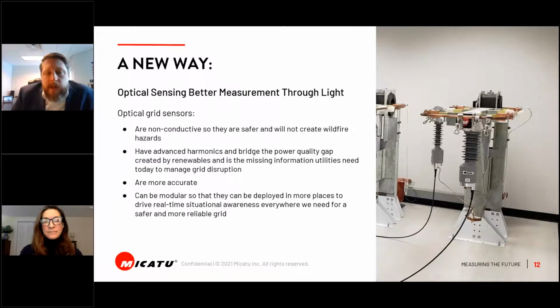The second thing is, because we're a field effect measurement technology, we have a large bandwidth. You're probably asking why bandwidth matters, it's because we can measure harmonics. Traditional technologies act like a low pass filter, whereas with ours we can measure up to the 250th harmonic in voltage and up to the 11th in current, and we're expanding the technology to measure even further. Harmonics for both current and voltage are of big interest to our customers, particularly around the status of equipment, power quality, and it's a great indicator for condition monitoring.